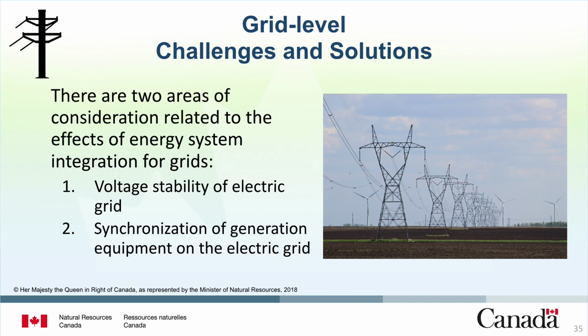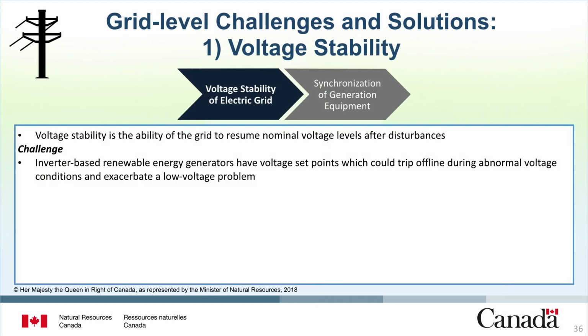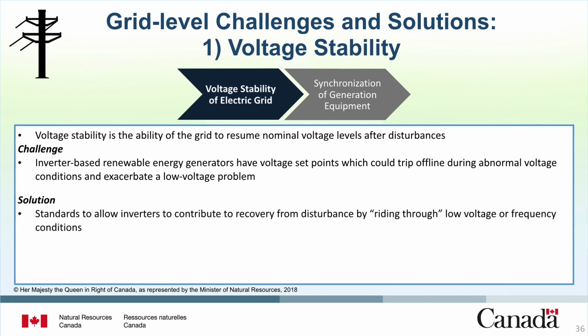We begin by discussing voltage stability of the electric grid. Voltage stability refers to the ability of the grid to resume nominal voltage levels after disturbances, such as sudden increase in load or sudden decrease in generator output, or other demands for reactive power that cannot be met. Renewable energy generators that are inverter-based have voltage set points, which could trip offline during abnormal voltage conditions and exacerbate a low voltage problem. A possible solution is for new inverter standards to allow inverters to contribute to recovery from such a disturbance by riding through low voltage or low frequency conditions. Such inverter standards involve non-unity power factor, low voltage ride-through, and low frequency ride-through.